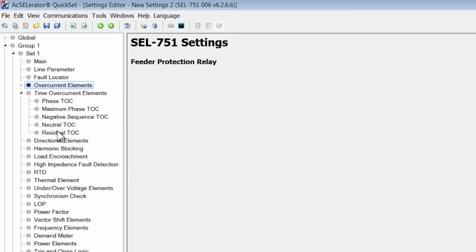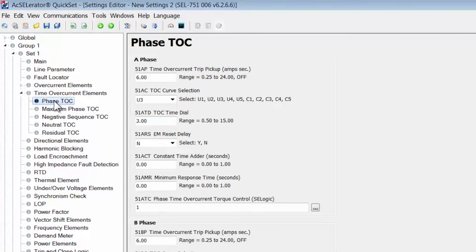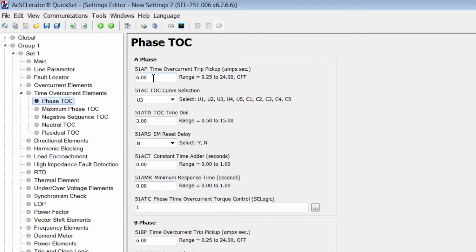Just to illustrate the simplicity, we're going to set a phase time overcurrent element and it's fairly similar to the 50 element only that the time overcurrent is dependent on a particular curve. Just like electromechanical relays, the time overcurrent element inside of the SEL relay chooses a curve.